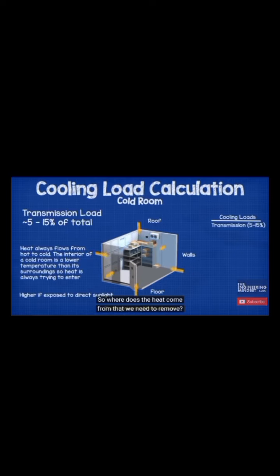So where does the heat come from that we need to remove? Well, typically 5 to 15% is through transmission loads. This is the thermal energy transferred through the roof, the walls and the floor into the cold room. Now, heat always flows from hot to cold, and the interior of the cold room is obviously a lot colder than its surroundings, so heat is always trying to enter the space because of that temperature difference. If the cold store is exposed to direct sunlight, then the heat transfer will be higher, so an additional correction will need to be applied to allow for this.